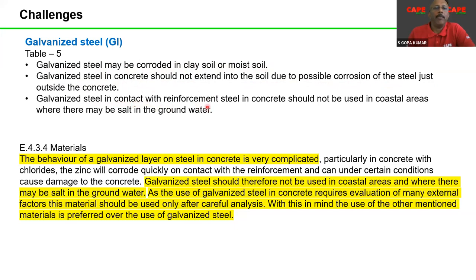Galvanized steel in contact with reinforcement steel in concrete should not be used in coastal areas where there may be salt in the groundwater. You see, one technique which is used is foundation earthing. If you look at the explanation of foundation earthing, the conductor is inside concrete and the concrete or the RCC floor is in soil. It is called wet concrete. A concrete or an RCC which is in soil is often called wet concrete. That means it has some wetness, and the resistivity of that concrete is approximately 100 ohm meter. That is what is specified in the standard based on several studies. So these recommendations are made.